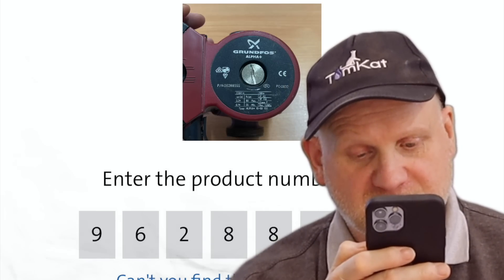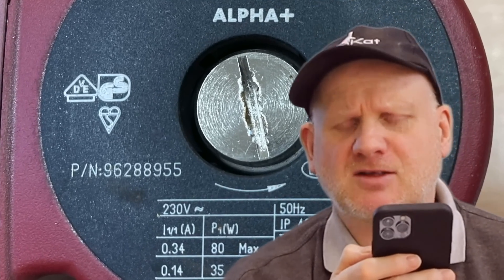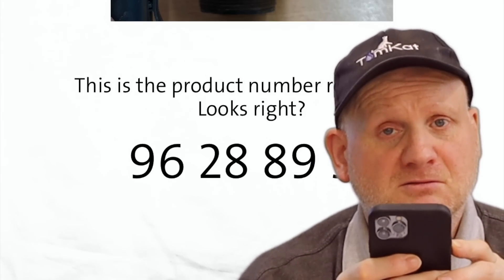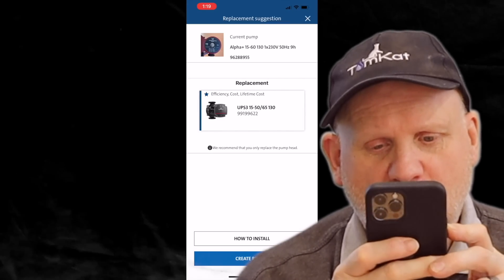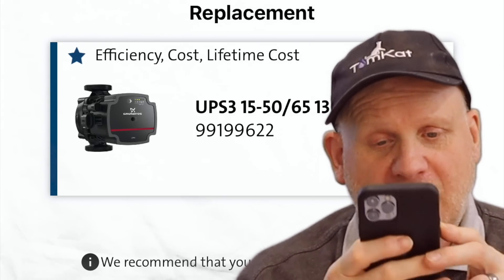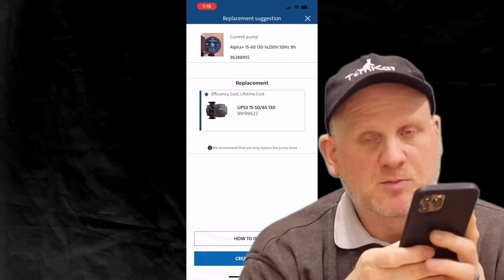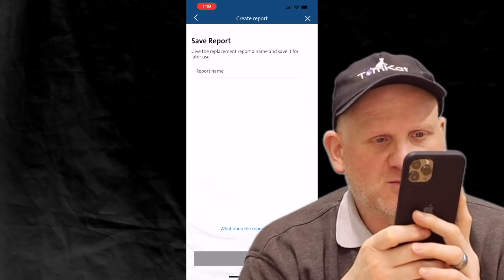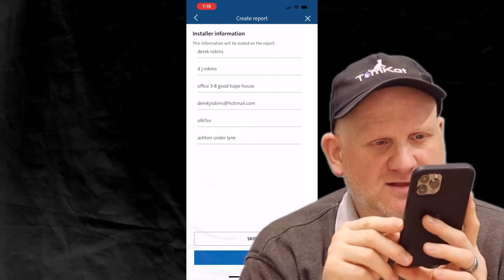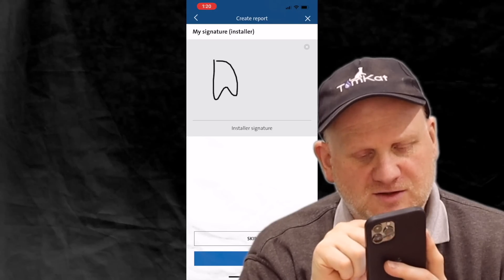It now gives us the product number - 96288955. If we look at the P/N number on the pump, that's correct. Press next and it says this is the product number registered - does it look right? Yes it does. Click on that and it comes up with a replacement pump: UPS3 15-50/65 130. It gives us a replacement pump for this one. We can also create a report - save it with a name, add install information, and sign for it.